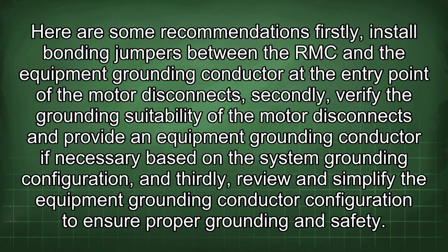Here are some recommendations. Firstly, install bonding jumpers between the RMC and the equipment grounding conductor at the entry point of the motor disconnects. Secondly, verify the grounding suitability of the motor disconnects and provide an equipment grounding conductor if necessary based on the system grounding configuration. And thirdly, review and simplify the equipment grounding conductor configuration to ensure proper grounding and safety.